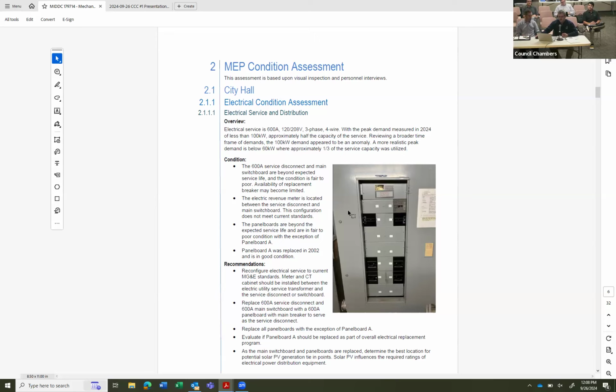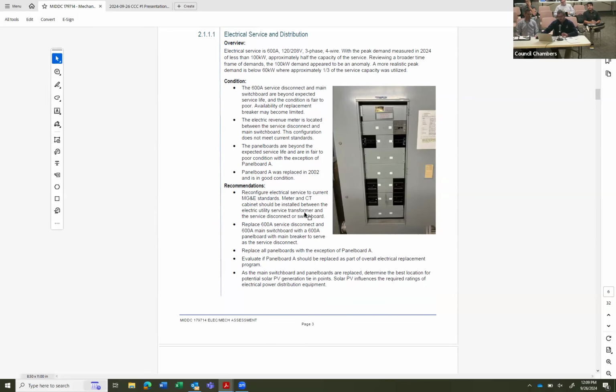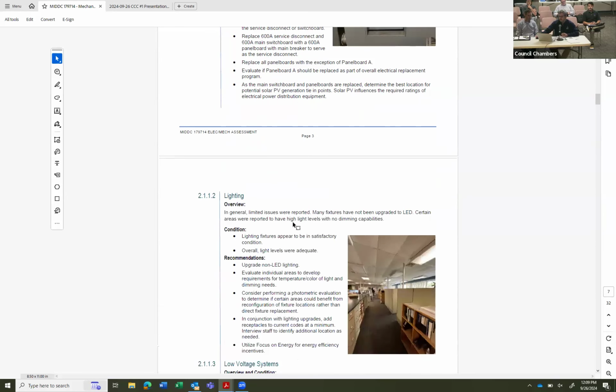And with the age of the electrical distribution equipment, I would recommend that be replaced as a part of it. But some key points in moving down to the panel boards throughout the facility: they all appear to be original to the facility, except there was one panel that was newer, but still around 2000, I believe, that would need to be reviewed to see if you'd want to replace it as part of other projects. It does still have a fair amount of life left in it because it's in a very temperature controlled place, not around high humidity and things of that nature.